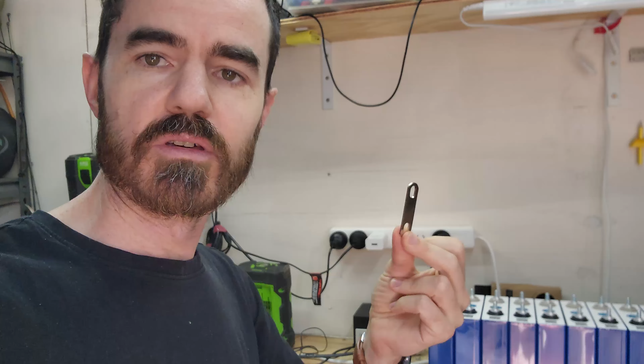The bus bars that came with them are these little 1.5 by 15 millimeter bus bars, and that's not really big enough for the current I want to pull. So I'm probably just going to double these up — put two on top of each other and screw them on. I've got more ordered as well, and for those I'll probably even triple them up just to handle the 200 amps or more current I need to pull through.